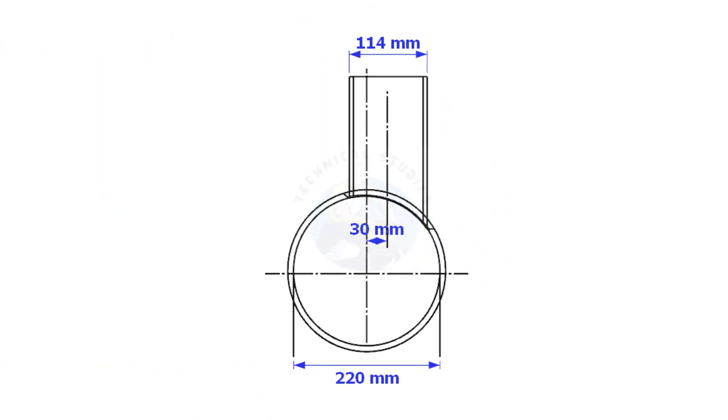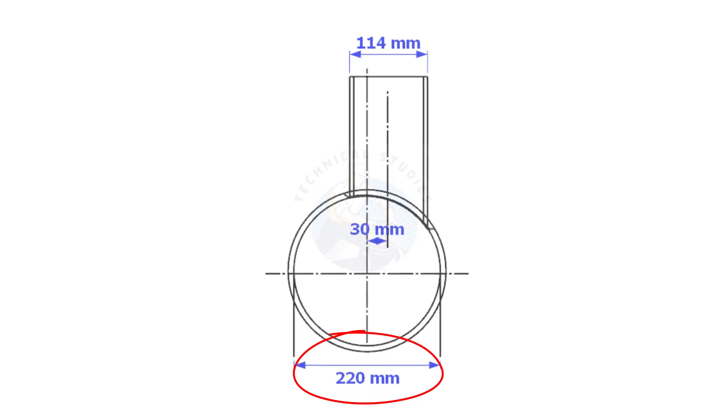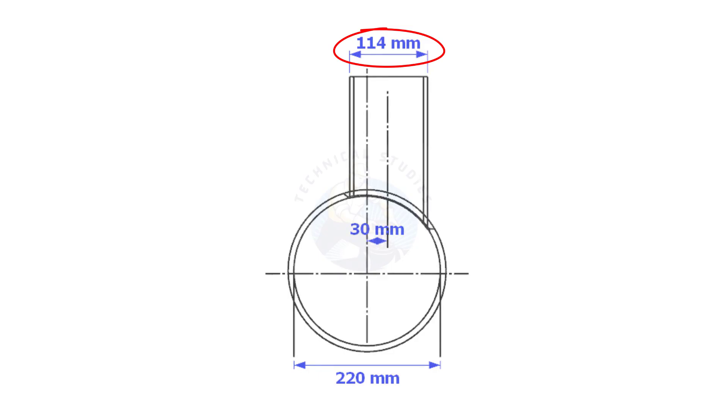Always consider the inside diameter of the header when you want to lay out the branch. Here, the header ID is 220 mm, the branch OD is 114 mm, and the offset is 30 mm.